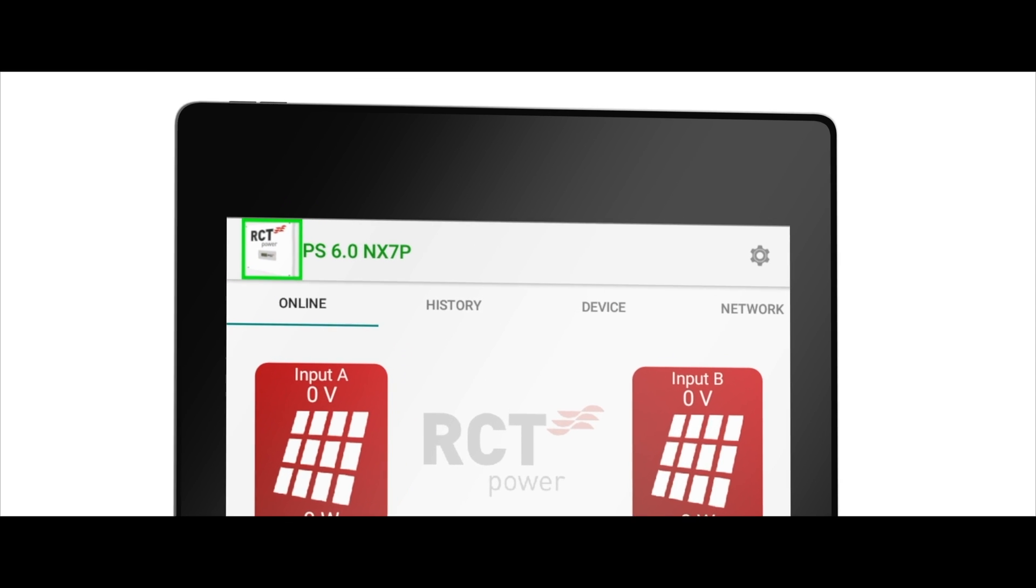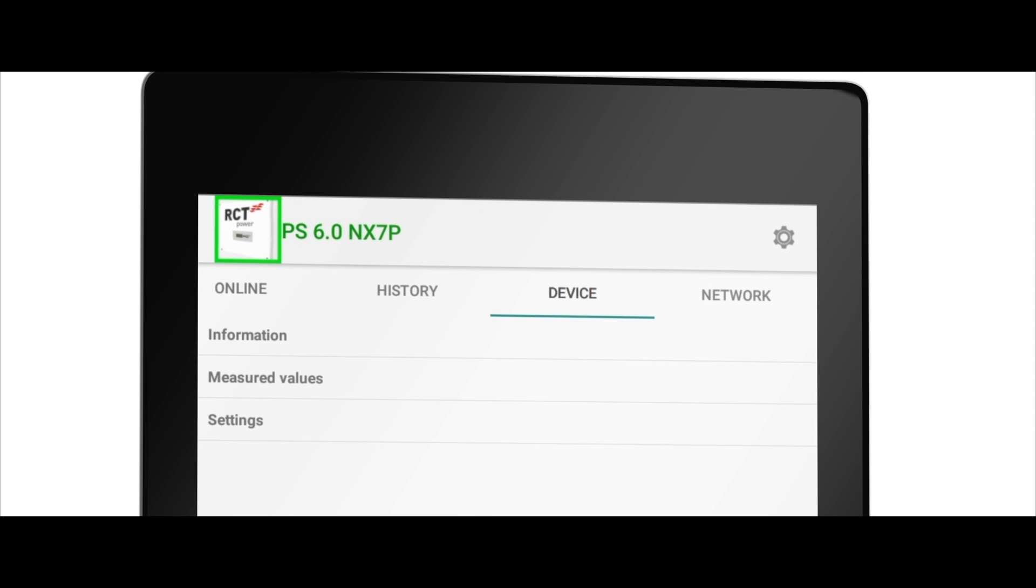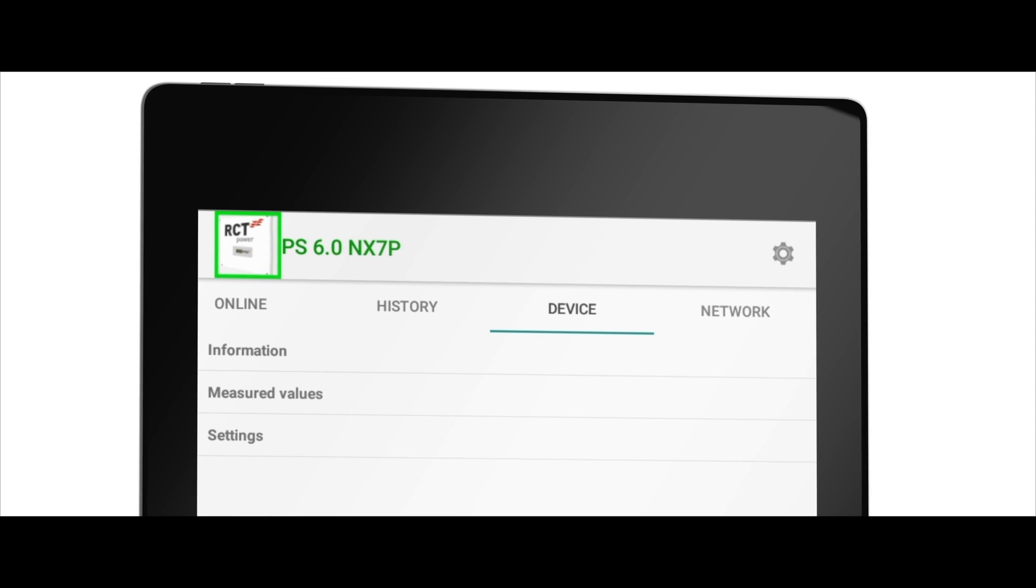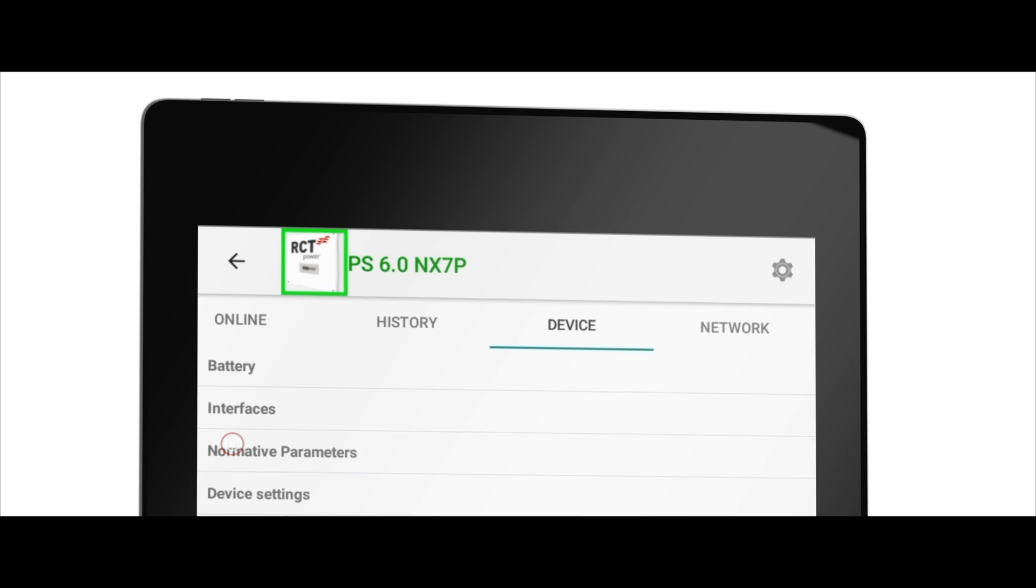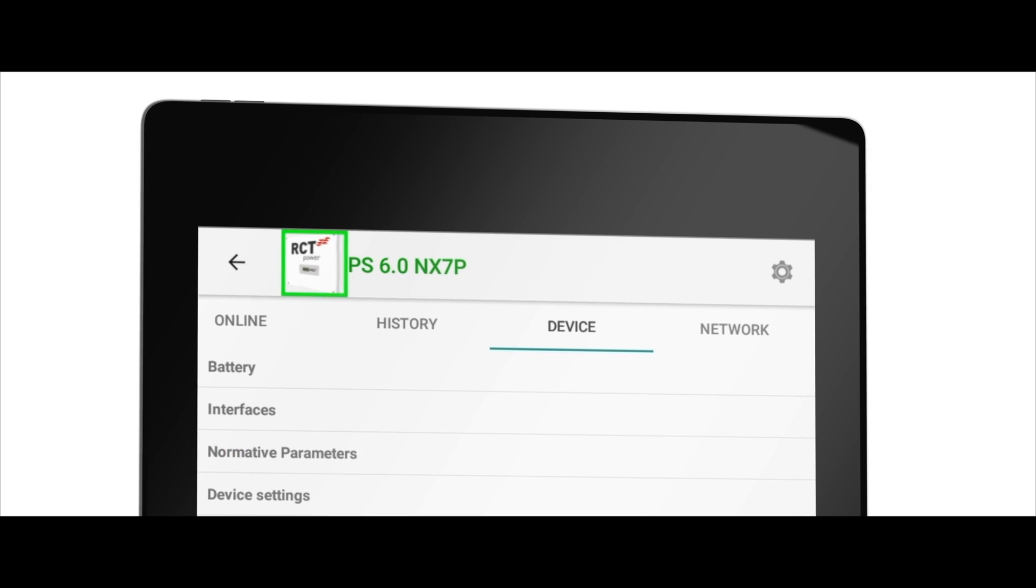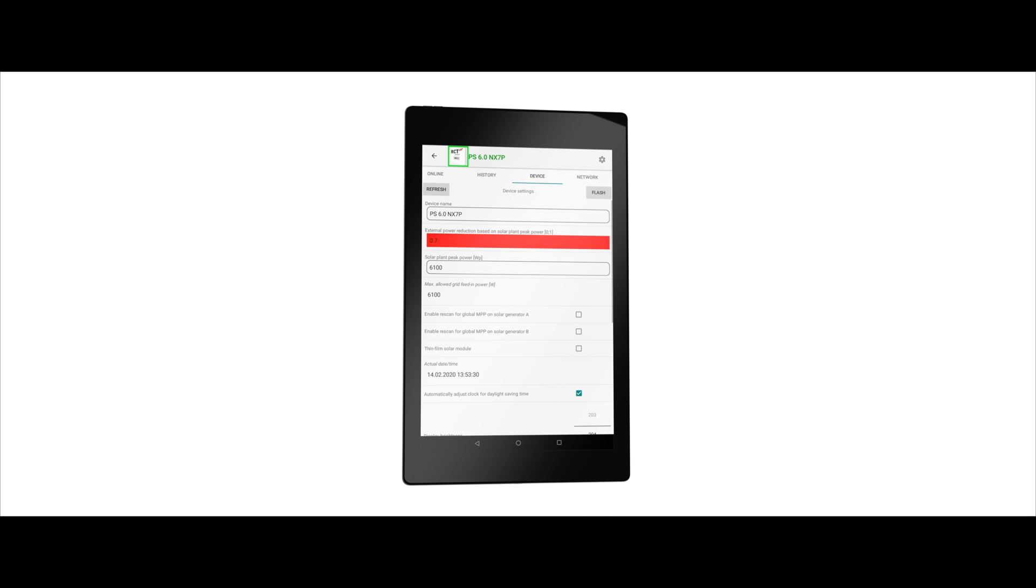Go to the tab device, select the option settings, and then device settings. Here you set the solar module power reduction based on your local requirements and the maximum power according to your solar modules as well as the prescribed power limit. After each entry confirmed with the enter key, the field is initially highlighted in red.